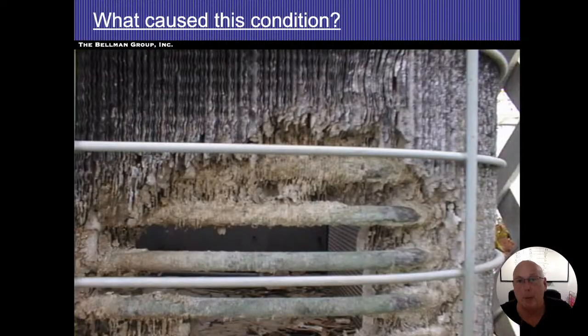All right. So just a couple pictures and a few things that we end up seeing here. I like this picture because it shows the tubes that the refrigerant is actually running through. And then it also has the fins on there that the air was flowing through. Now, this happens when a dog urinates on the air conditioning system. Those fins are very thin and they're fragile. A dog's urine sometimes is pretty acidic. So if they keep peeing on the air conditioner all the time, then it wears away at the fins.